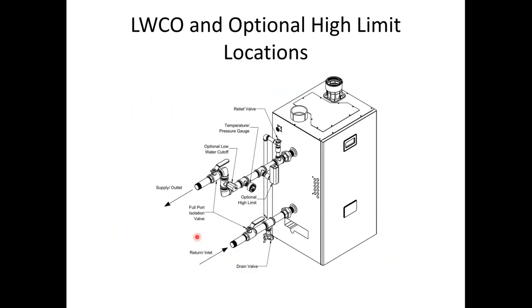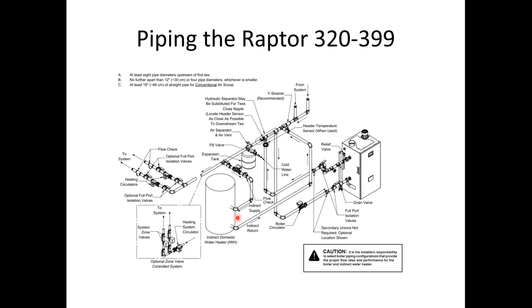The 399 and 320 do not come with a port for the low water cutoff. We show where they would be optionally piped, and if you were using any of the CSD-1 manual reset high limits, it shows where they would like them to be piped. There is a harness kit for the low water cutoff, and it will plug into the Raptor's PCB board. And again, here we go, laying out piping for the 320, 399. This drawing is showing the indirect tank piped in the system as a separate zone. The reason I'm using two different pictures for the boilers is to show the different piping options that we can offer.